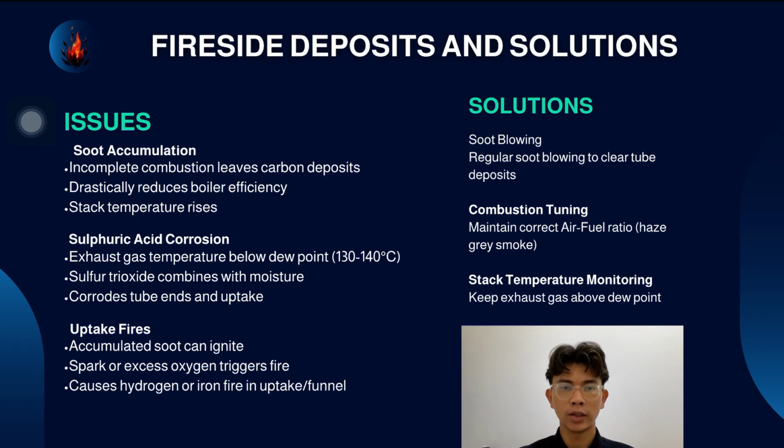To solve this, we need regular soot blowing, proper combustion tuning to maintain a haze grey smoke, and we must monitor stack temperature to keep it above the dew point.